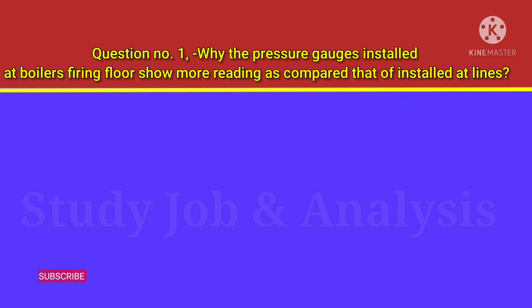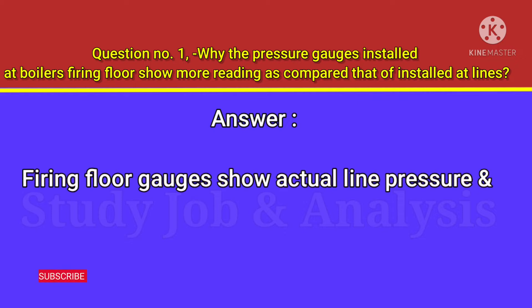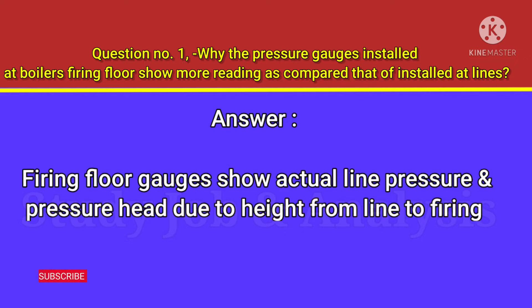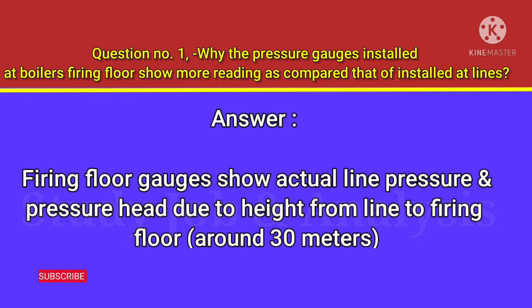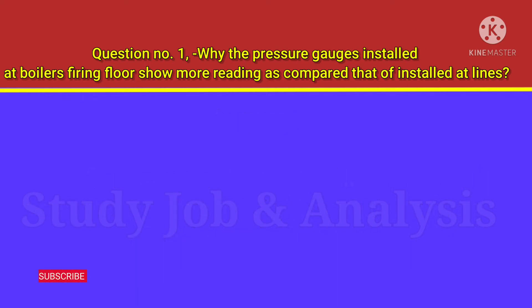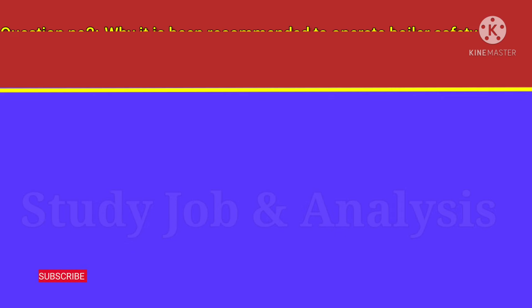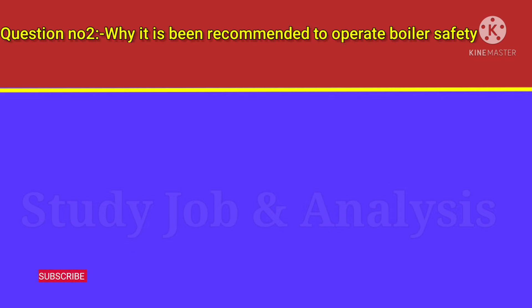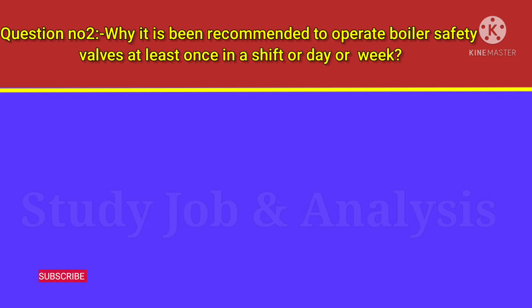Answer: Firing floor gauges show actual line pressure plus pressure head due to height from the line to firing floor, which is around 30 meters. Question number two: why is it recommended to operate boiler safety valves at least once in a shift, day, or week?